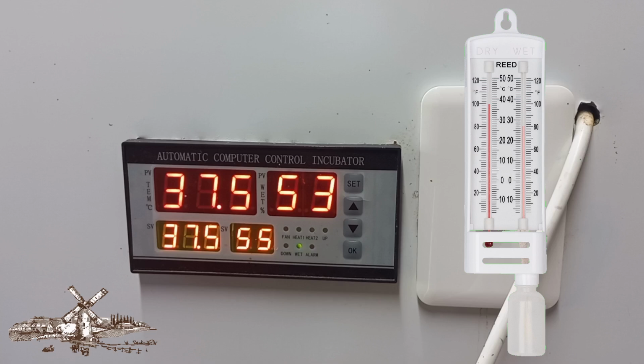We are going to determine what the real humidity is. We are then going to determine what we have to do to the controller value to make it the same as the correct value. And we will then adjust the F6 value this time, because F6 is my humidity calibration value. Now, in order to determine what the real humidity is, it's slightly more complicated.